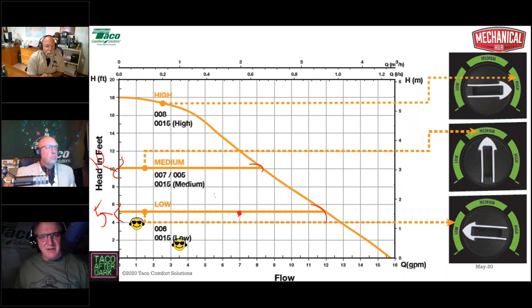It's going to be right there. All right, 7 gallons a minute, 5 foot head, I'm working right here because here is the system curve. All right, 7 gallons a minute, 5 foot head, she's going to be working right there. Okay, and bingo. 1 gallon a minute at 4 foot head, that's my smallest zone. Well, it can't work there. It has to work up here at maybe 1.25 gallons per minute.